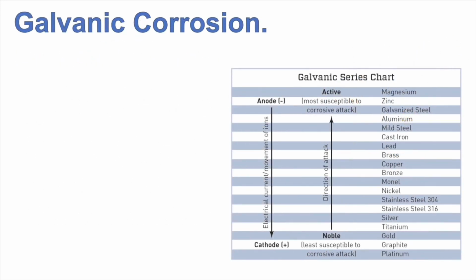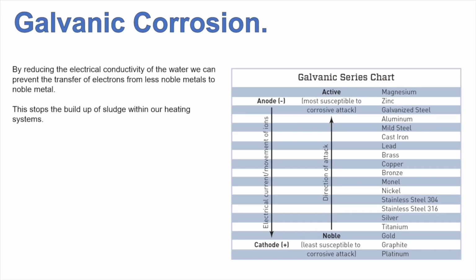Here we have our galvanic series chart, and as you can see, the metals are listed in order. We have what would be classed as anodes at the top and the cathodes at the bottom. This shows where metals will pass electrons from one metal to another, depending on how noble it is within this series chart. This is important to stop galvanic corrosion.